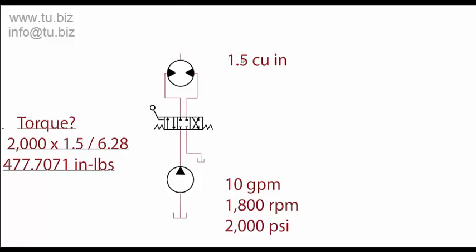Something to watch, however, is if you increase the displacement and you have the same gpm going through a bigger motor, then the rpm of the motor itself is going to go lower.